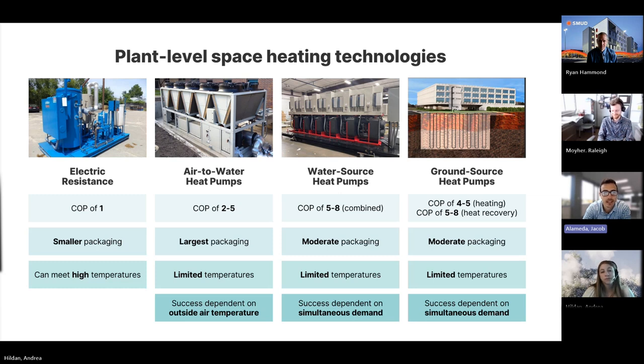So I guess next in line are air-to-water heat pumps. These units give you a little more efficiency because instead of creating heat, you are moving heat using the vapor compression cycle to take heat out of the air and put it into your heating water source. Moving heat like that versus creating it allows this equipment to get you COPs between like 2 and 5. At design winter temperatures in the Sacramento area, typically those units will drop down to a COP of like 2.4, but on average they'll come out to around 3.